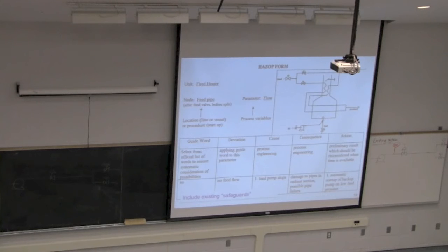This is an important point. So no feed flow, caused by a variety of reasons. The first one written here is that the feed pump stops. So this pump over here feeding the furnace stops. It quits on you. And the consequence of no flow in these situations could be damaging the piping inside the furnace.